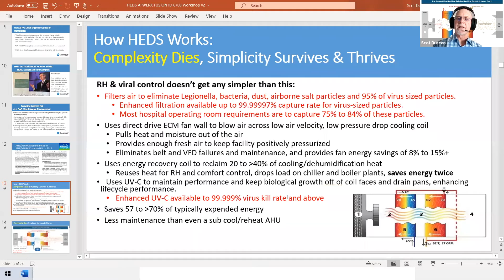So I'm going to skip to the next bigger one. This is how simple HEDS is. This is a replication of an air handling system. Starting on the left-hand side, you've got 95% to 99.999% air filter banks, versus a normal air conditioning system, which has a 20% effective filter bank. Hospital OR requirements are typically in that 75 to 84% range. So the 95% is our normal off-the-shelf; we would put that on any base anywhere. For more critical applications, we've got the 99.999% version of it, and then UVC also.